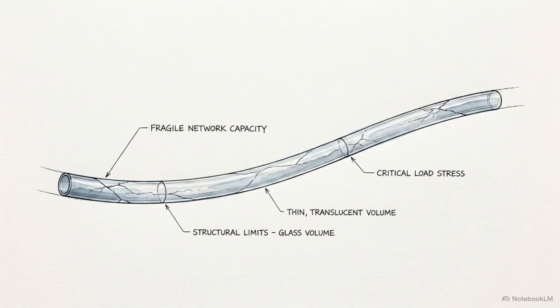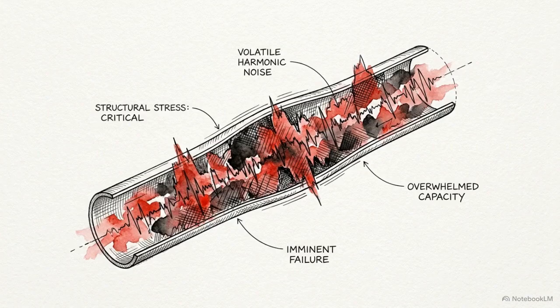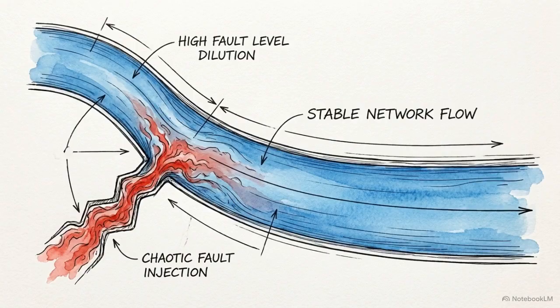Think of a weak electrical network like a narrow pipe. If you inject a small amount of dirty harmonic noise into it, the entire pipe is instantly polluted and overwhelmed. But a massive, highly connected network operates like a rushing river. It can absorb and instantly dilute that same amount of pollution without failing. This chart tracks grid responses to frequencies. The peaks on this curve represent natural resonance points, where harmonic noise is dangerously amplified. As the arrow shows, increasing the fault level shifts the resonance peak to a higher, safer frequency band, preventing amplification.